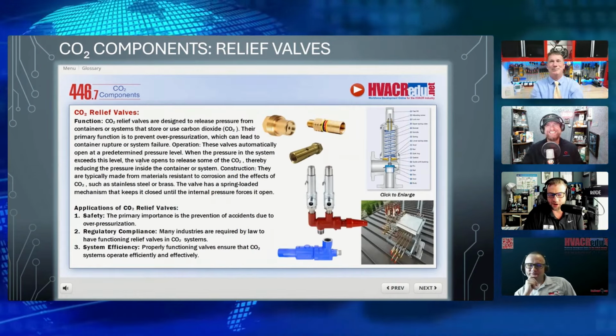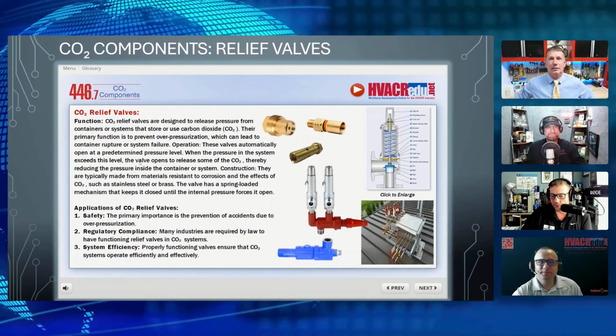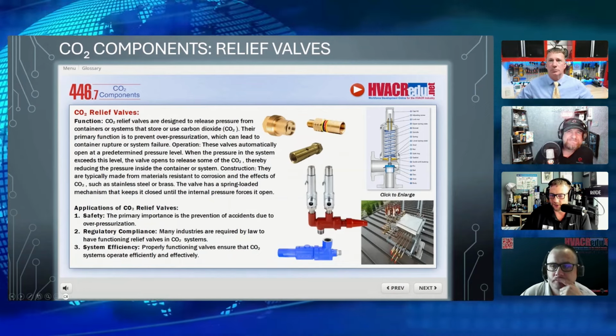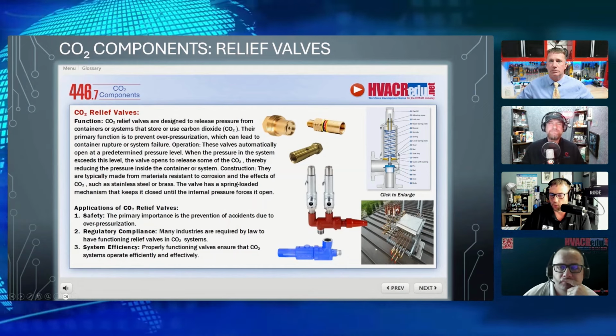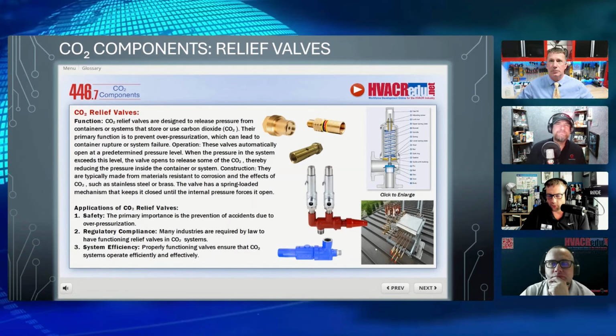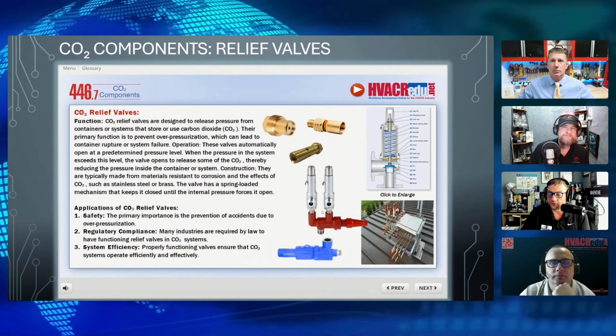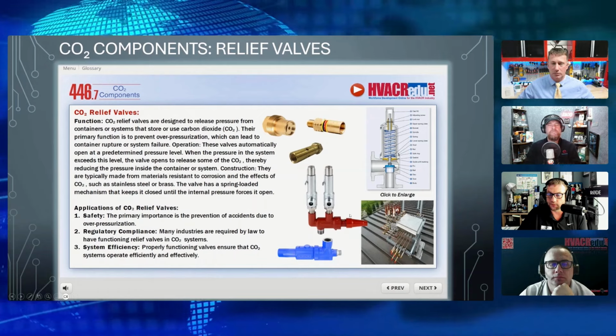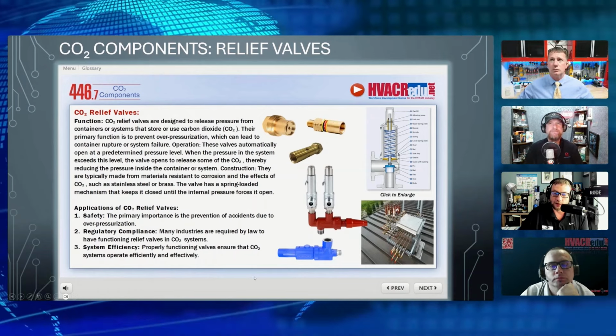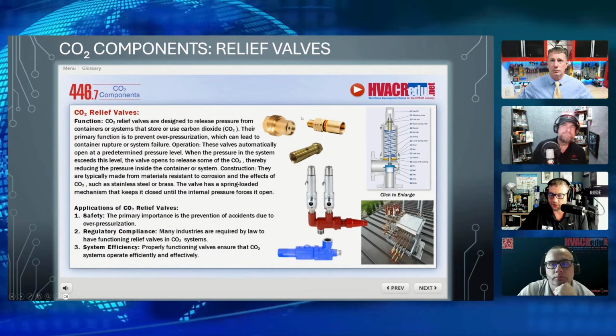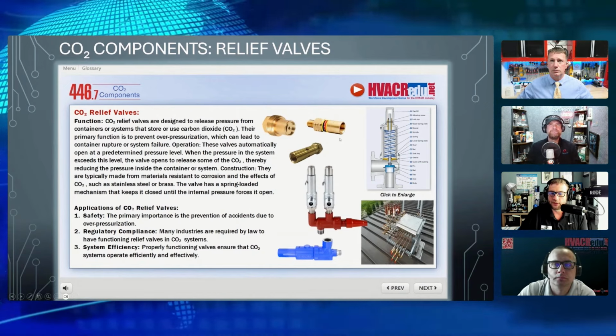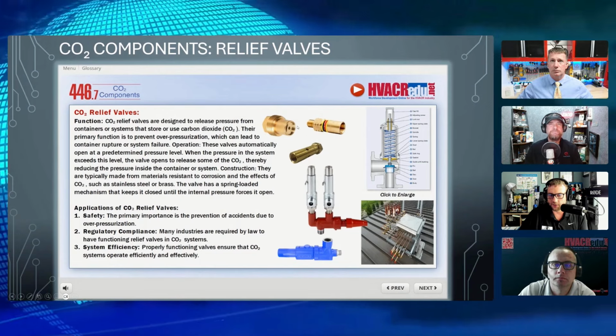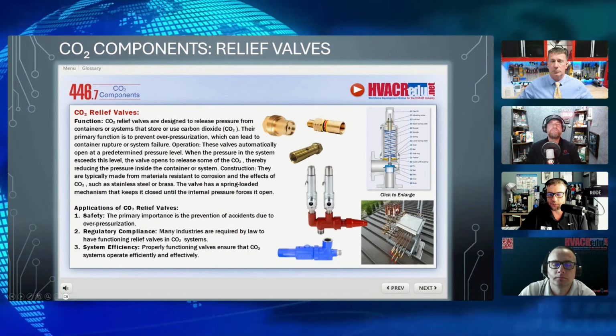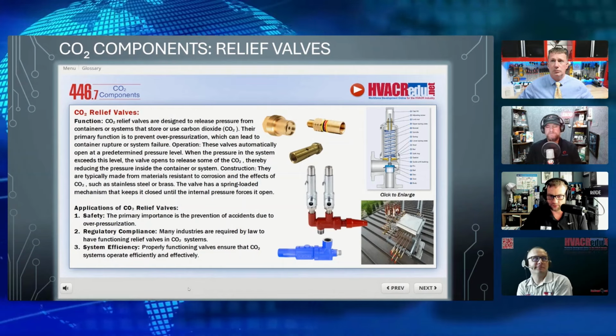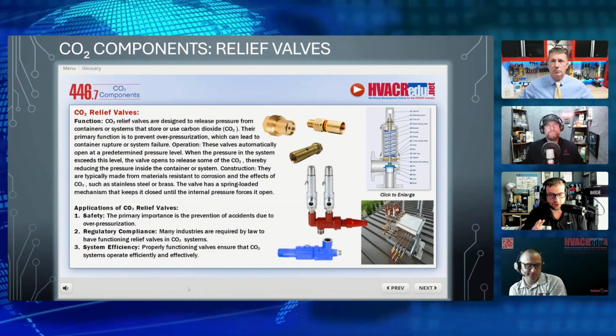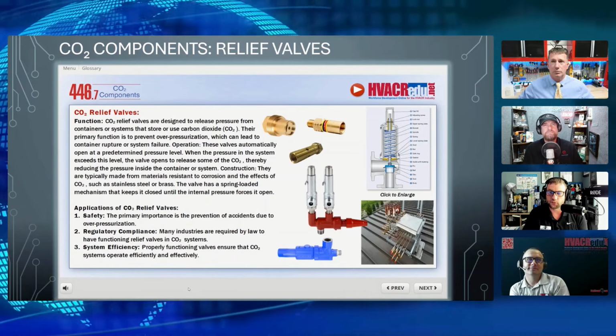So on this, I broke down the different reliefs. As you can see in the bottom right-hand corner, that is a relief doghouse. You can see a lot of these different reliefs that I have labeled here, and what system. Yeah, and what system. So like the big red and blue one, those would be something you'd see on the discharge or the gas cooler, right? Those typically release at like 1740. The one with the little tag up at the top can be 635, 435. And those two right there are compressor reliefs. Typically, even though the main relief blows at 1740, on the compressor ones, and I'm not sure about every single manufacturer, usually it's about 2180 is what those relieve at.